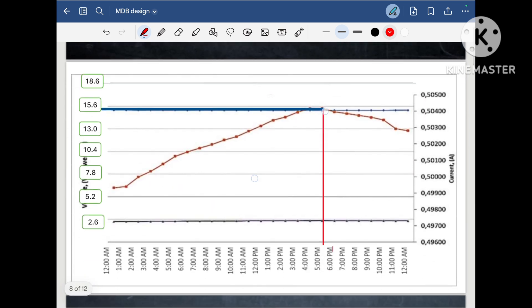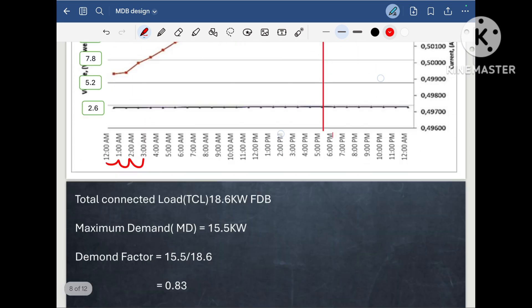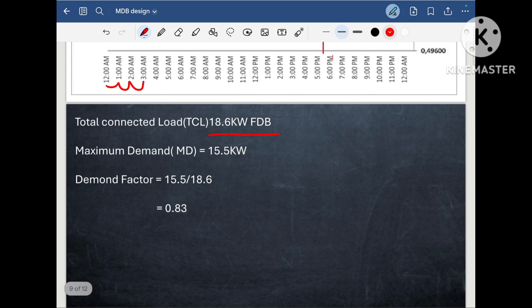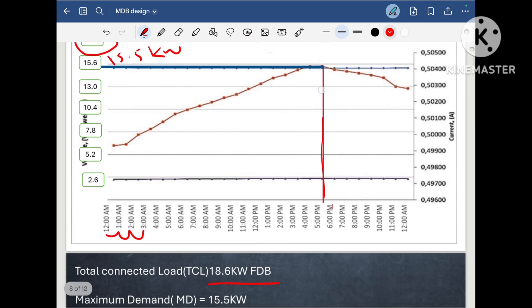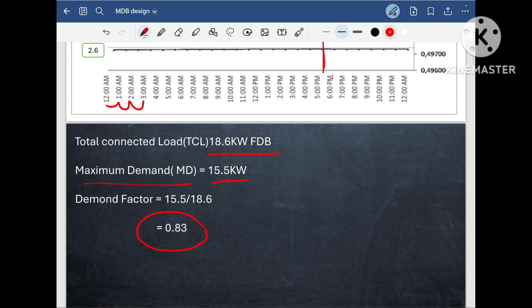Our total connected load is 18.6 KW. I tabulated what load is running at a particular time at each hour, the same as the previous example. Then I found that at 5:30 the maximum load is running for this flat, that is around 15.5 KW. So our total connected load is 18.6 KW and the maximum demand is 15.5 KW from this graph. So the demand factor is 0.83.